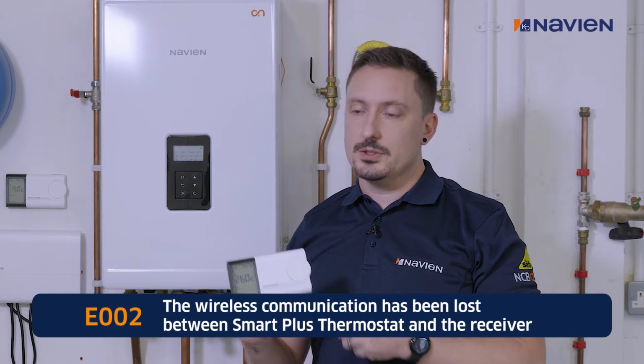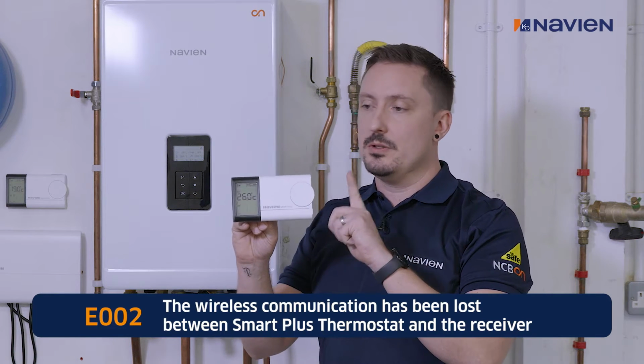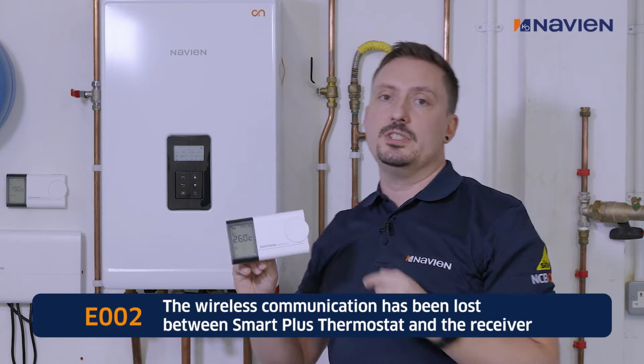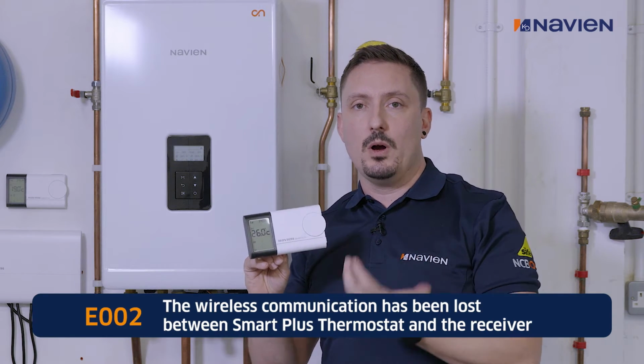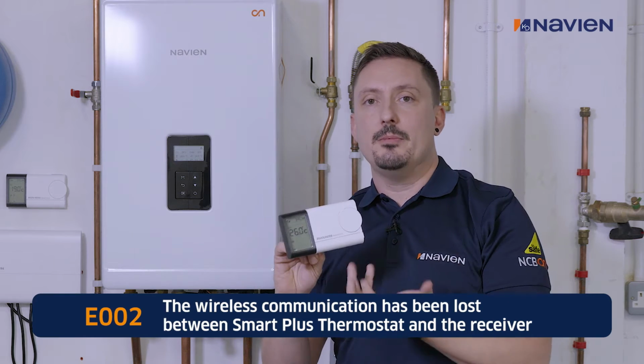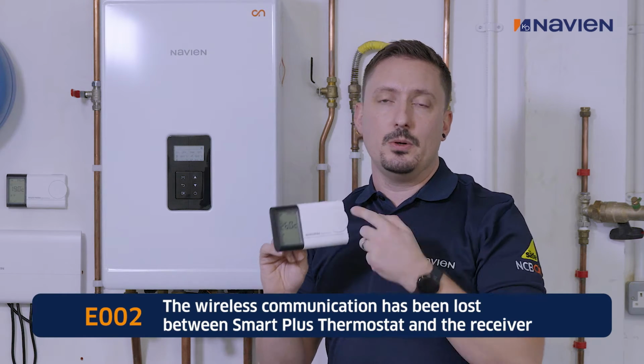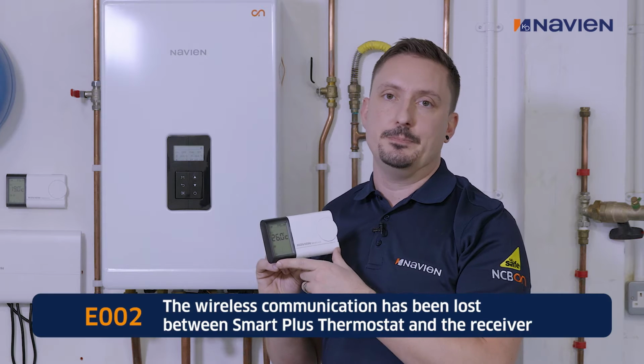Then you'll have E002, which means that you have lost wireless communication between your room thermostat and your wireless receiver, and you just need to check that wireless connection. Either you may have poor batteries or weak batteries, or this is too far away from the receiver.